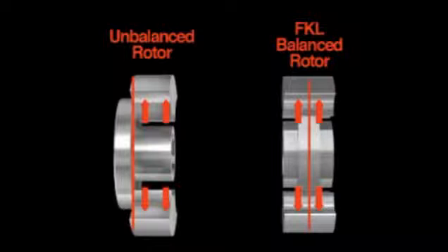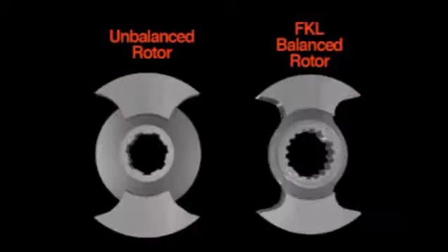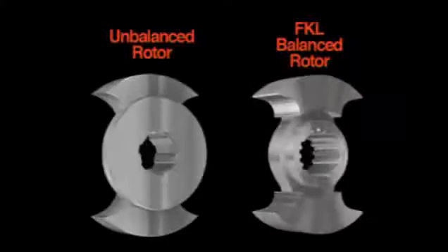With an unbalanced rotor, the lobes are cantilevered. When high pressure is applied to an unbalanced rotor, the support bends. As the support bends, the lobes contact the housing, causing wear to both.